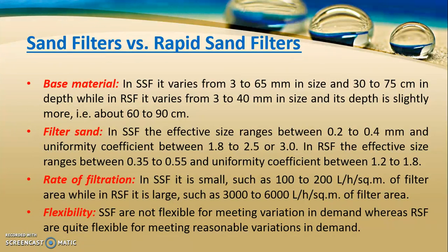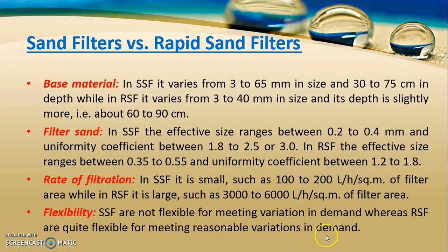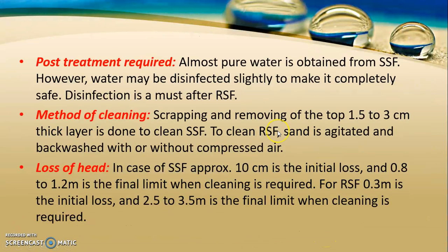Comparing slow sand filter versus rapid sand filter: the size of sand and gravel in slow sand filters is comparatively finer than in rapid sand filters, which is why slow filters have a lower rate of filtration. Slow sand filters are not flexible for meeting variations in demand, whereas rapid sand filters are quite flexible. Water from slow sand filters is almost pure and may only need slight disinfection, whereas disinfection is compulsory when using a rapid sand filter.